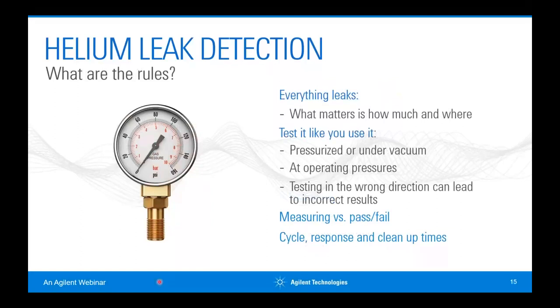Some basic rules with leak detection. The first one people find hard to accept: everything leaks. When I ask customers what their specification for leak testing is, the uninitiated may say they can't tolerate any leakage. But at some level down to the molecular level, your product will leak. What matters is how much it's leaking and where, so you can find those leaks and fix them or reduce them to a point where they're inconsequential.